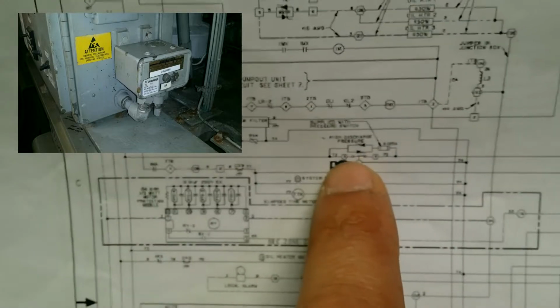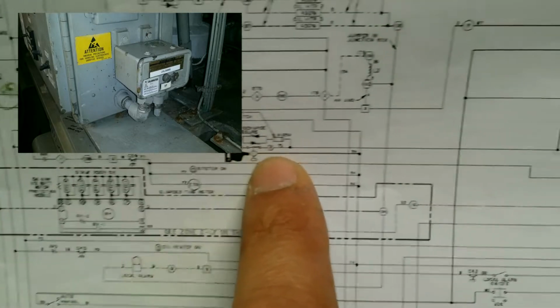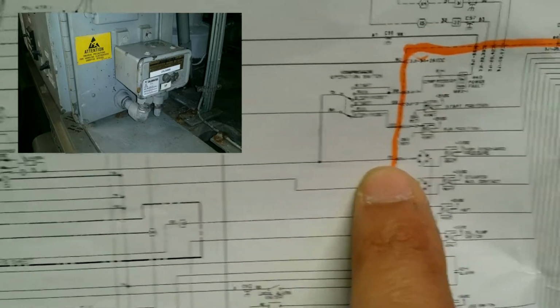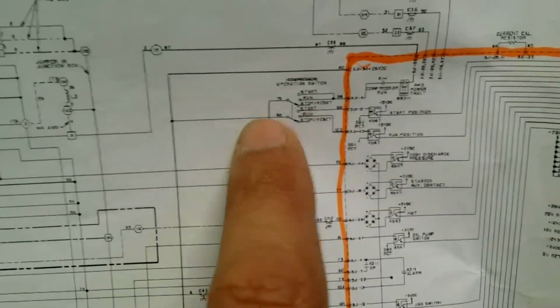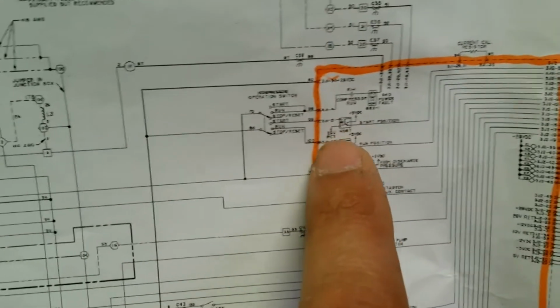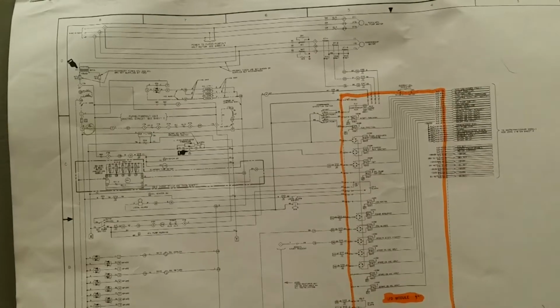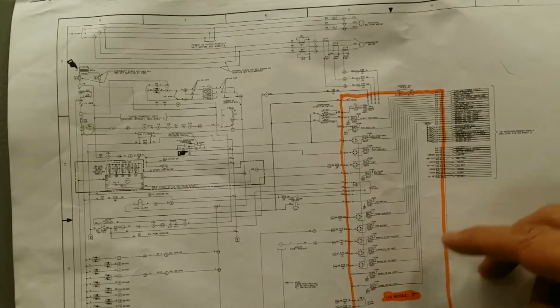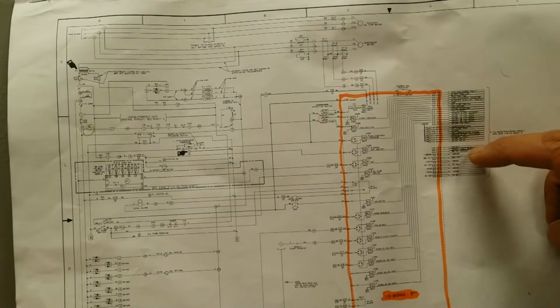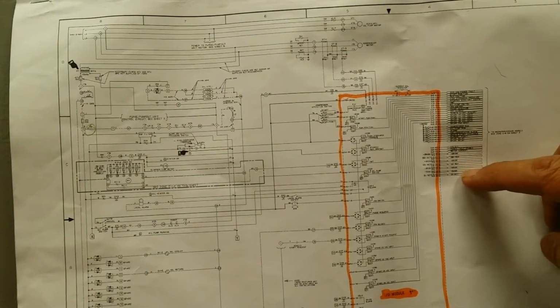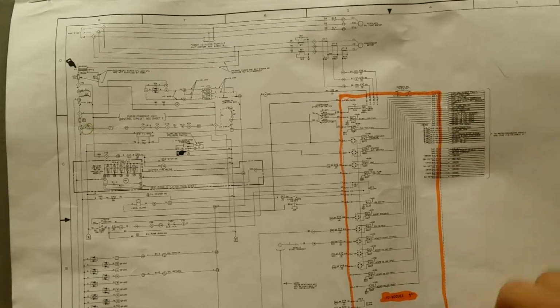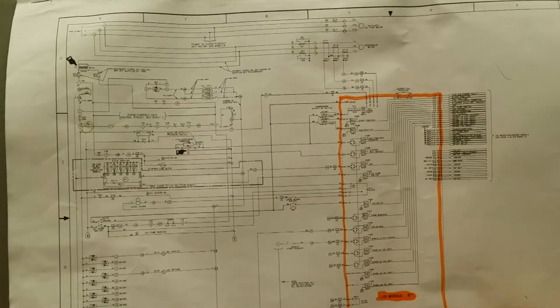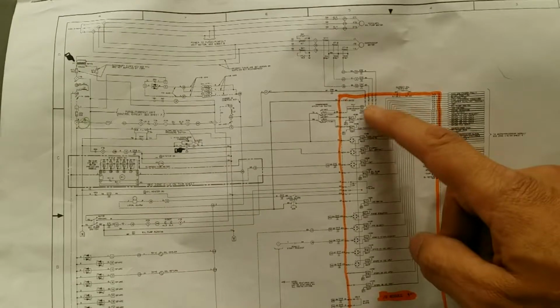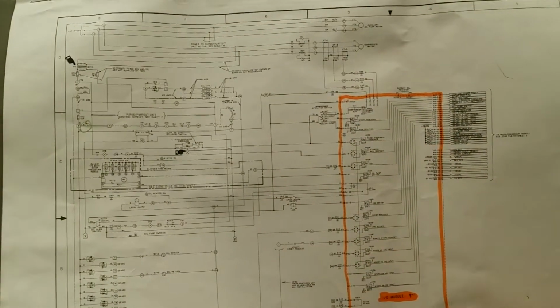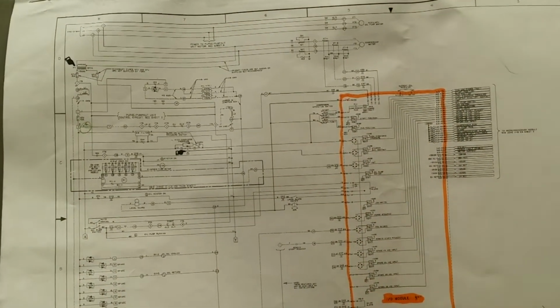And I almost forgot to talk about the high pressure switch. As you can see, it clearly provides a direct input to the input and output card, and is also a required input to be able to start the AC. The last thing that I'll tell you about this card is that it gets all the voltages, 28 volts, 5 volts, and so on and so forth, from the microprocessor card. It has a total of 8 relays, 2 of which I talked about. The other ones I didn't go into much detail on because in my AC they are disabled.